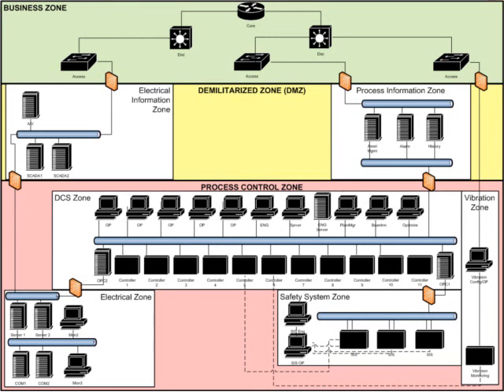We decided, working with the client, to apply the Purdue reference architecture to their system. This resulted in zoning their system into three main zones: a business zone, a demilitarized zone, and a process control zone, each with subzones. In the case of the process control zone, we broke it into a DCS zone, an electrical zone, a safety system zone, and a vibration zone.